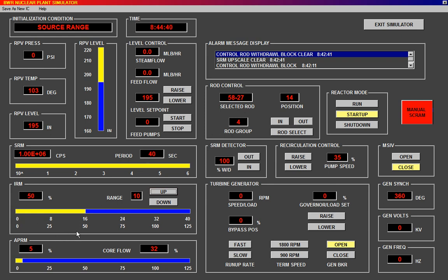We're still in exponential growth, but if you realize the period is getting higher and higher. So you can see that this exponential curve is becoming a logistic curve. Why is this happening? Because the pressure vessel temperature is increasing. You see we had 100 at the beginning, we had 107, because we start to have an important power being generated by the activity, and this is creating bubbles of boiling water. So this changes the moderator characteristics of the water in the reactor, and this decreases the reaction. So at this moment we reach equilibrium. Actually now we have a decrease of the activity, as we see with this negative period number here.